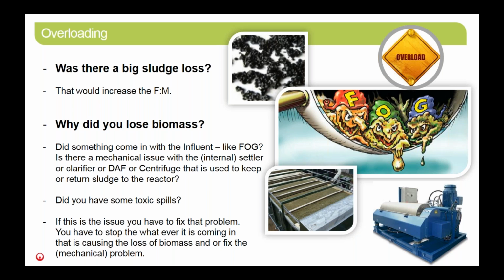If you have a lower rate system that's returning sludge via a clarifier or a dissolved air flotation unit or a centrifuge, any one of those could have a problem and cause a lack of sludge return and a loss of sludge. And it could also be due to a toxic spill. So obviously, if a mechanical issue is the problem, you want to stop that problem by keeping the equipment maintained in a good manner and keep the mechanical problems at a minimum.